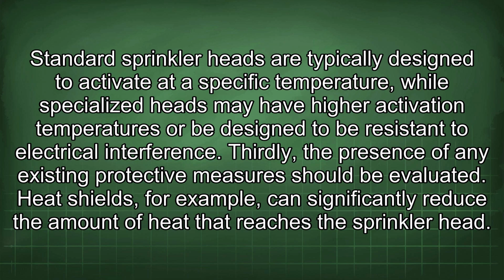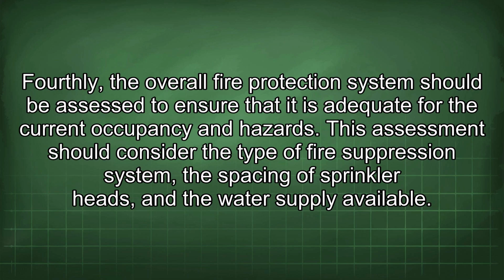Thirdly, the presence of any existing protective measures should be evaluated. Heat shields, for example, can significantly reduce the amount of heat that reaches the sprinkler head. Fourthly, the overall fire protection system should be assessed to ensure that it is adequate for the current occupancy and hazards. This assessment should consider the type of fire suppression system, spacing of sprinkler heads, and the water supply available.